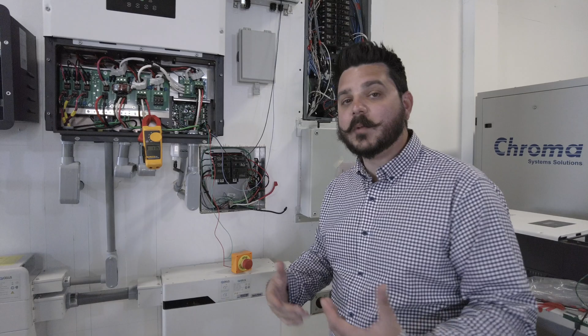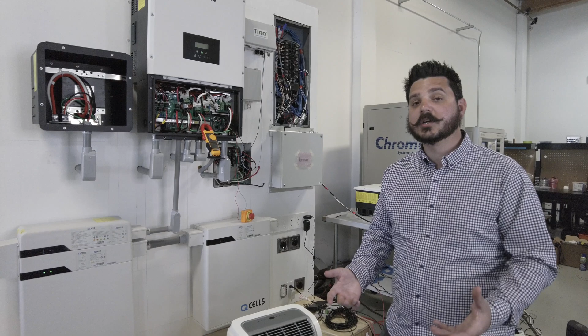Right now this panel has 6 circuits on it, but these are pretty large loads indicated here. So it's all about your loads, and we balance your system to ensure you don't overload it, because you could. If you overload your backup system, whether it's a Q.HOME or any other, the system will shut off and then you have no backup power. So it's important to manage your loads during a power outage, but also not to go overboard stuffing as many loads as you can into the backup panel, because then the system just won't work properly.